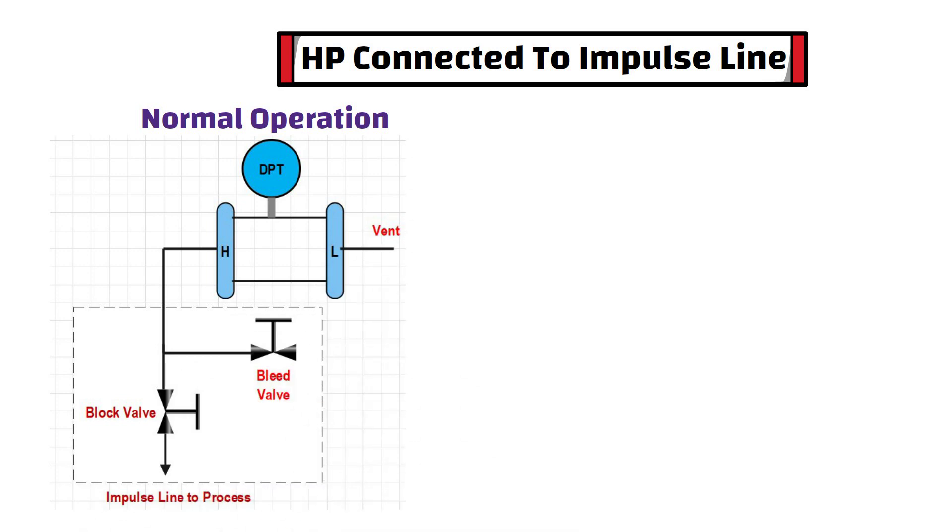Let's take one more example, when only high port side of DP transmitter is connected to impulse line and low port side remains open to air. As you can see, in this situation, in normal operation, block valve is in open condition and bleed valve is in closed condition.